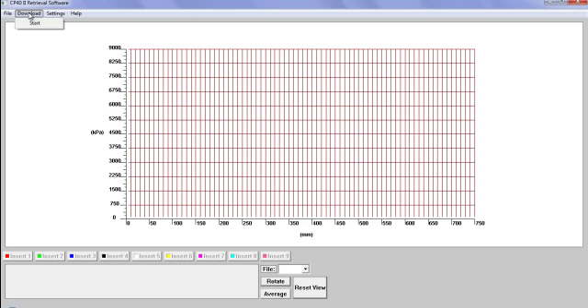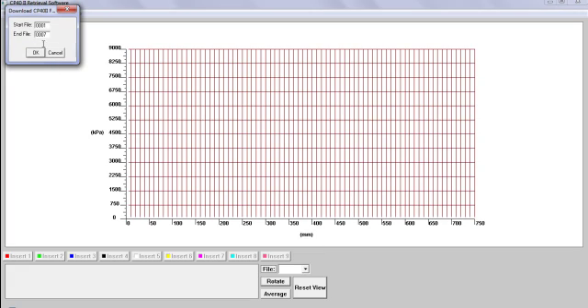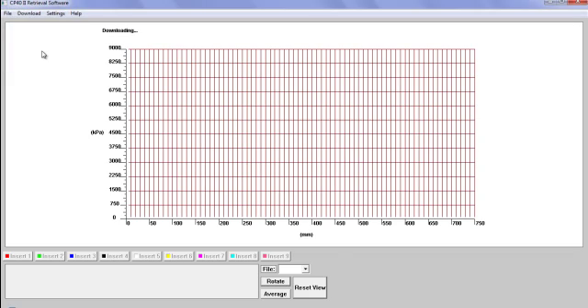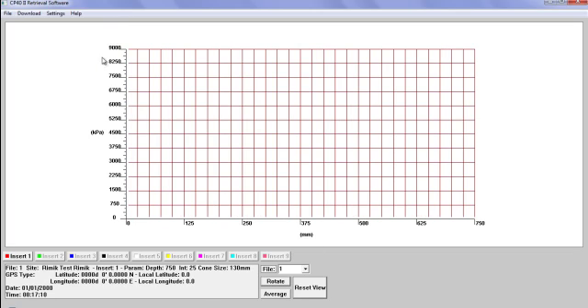Now I can download. I hit the Start button and it tells me that there are files one to seven on the instrument that I can download. I say OK to that and we see the message downloading. When it's finished, we'll get the information down here.